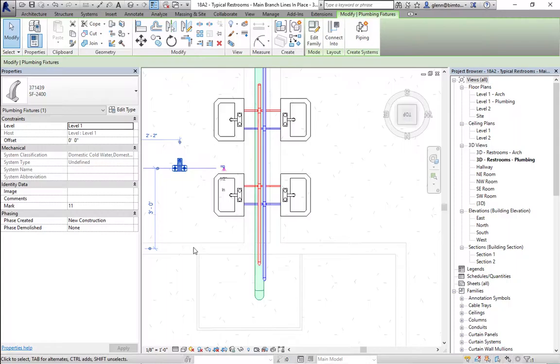Henry asks: for the open and close of a faucet, is that not a constant flow? Think of the rating as the maximum flow. When we do flow rate calculations we consider the worst case — if everyone flushed the toilet at the same time and all the faucets were on at the same time. A nice simulation might show we probably need only 40% of that capacity based on how people actually use fixtures, but in the worst case — like the Super Bowl just got out and this is the one restroom in the stadium — that faucet may be running constantly.